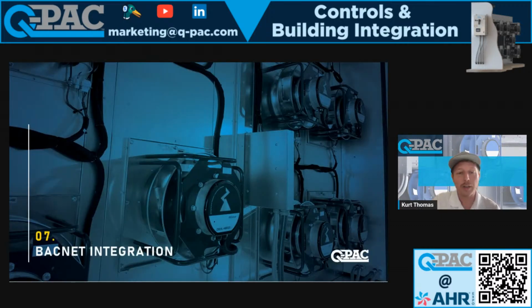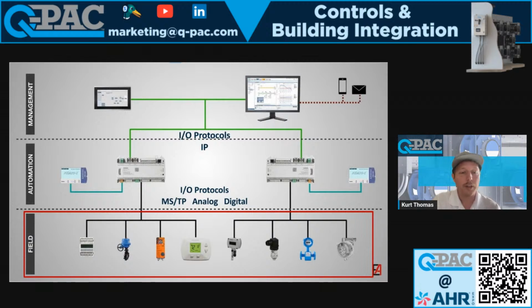BACnet. Here we go, Frank. So normal operation or normal structure of the building automation system protocols are the field components, right? And those are here all at the bottom in the red box. We fall in that field. We are a component. Right now, we communicate via BACnet MSTP.